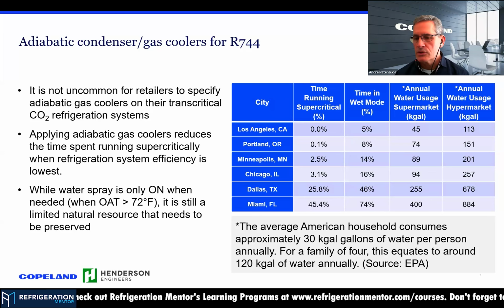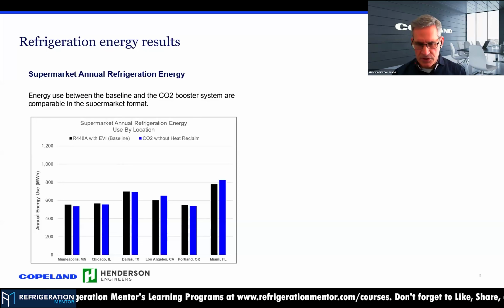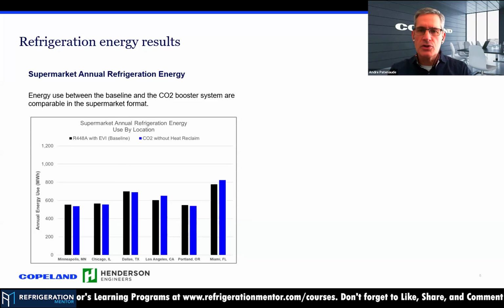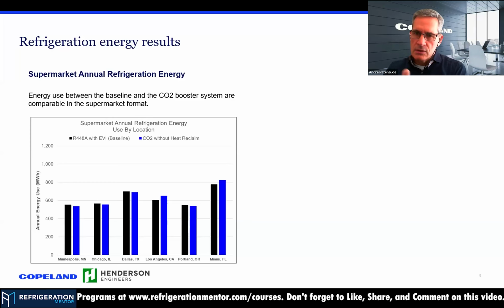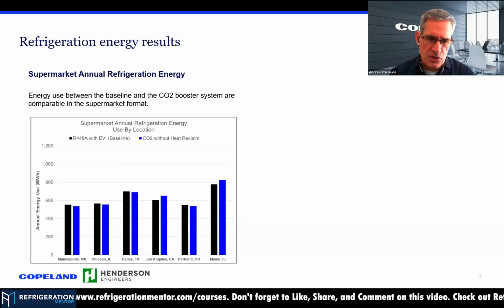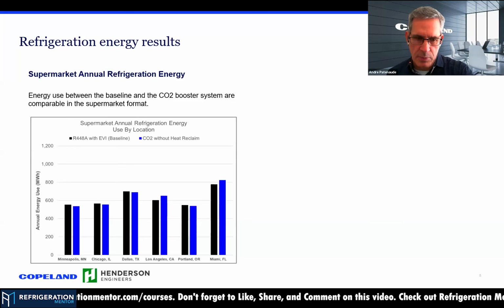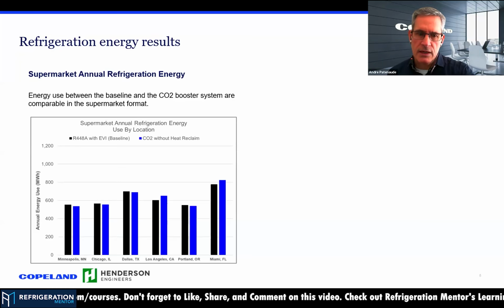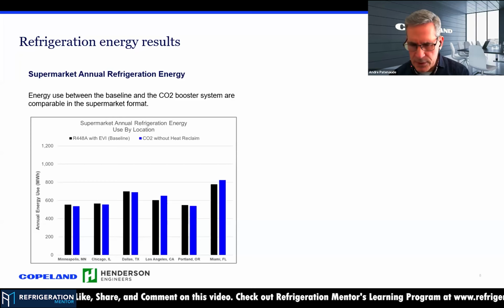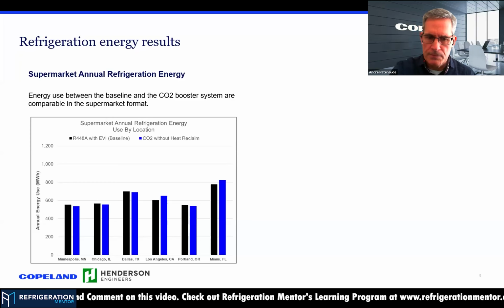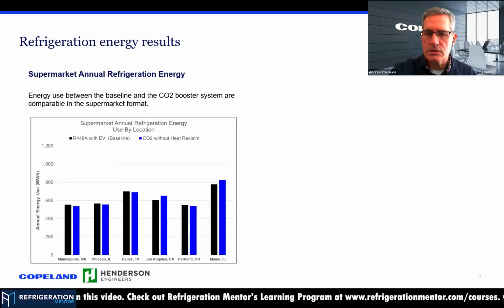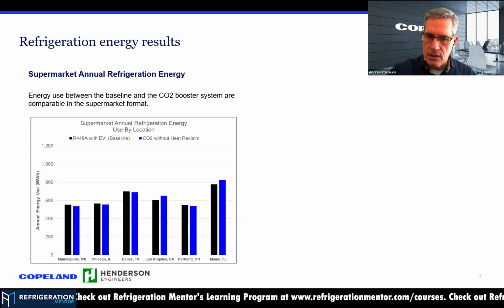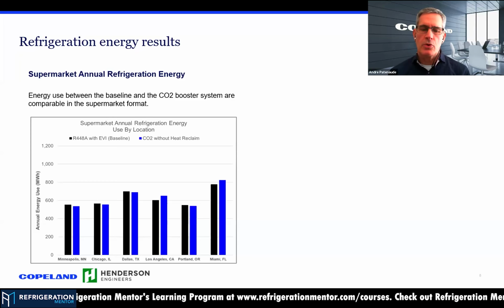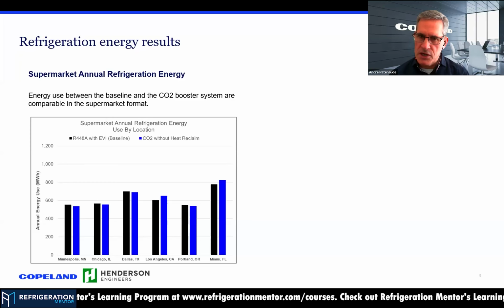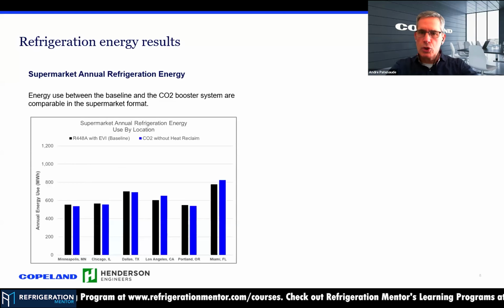Awesome. So the next slide shows, I believe, energy. This is interesting - supermarket energy only, without heat reclaim in this case. Trevor will be talking about layering in heat reclaim, but this was interesting because you take Minneapolis at the very bottom left: the dark black line is 448 with EVI, the blue is CO2, and you can see CO2 has a little bit of an energy advantage with adiabatic gas cooler in every region except Los Angeles, where CO2 is a little bit higher, and Miami, a little bit higher. Remembering that the percentage of low temp loads was 29% of the total load for supermarkets.